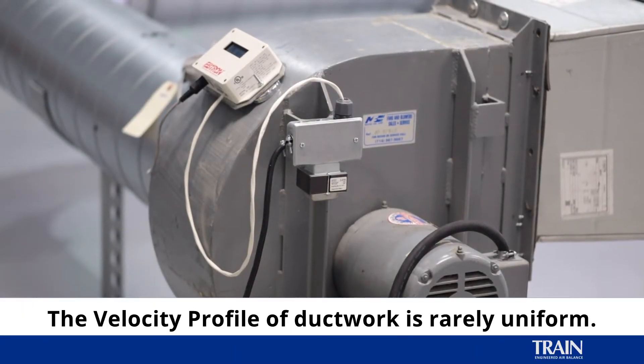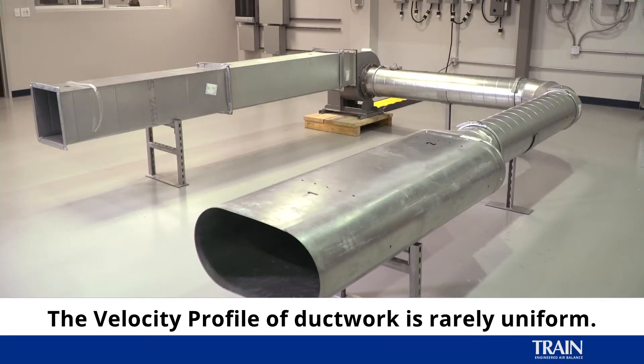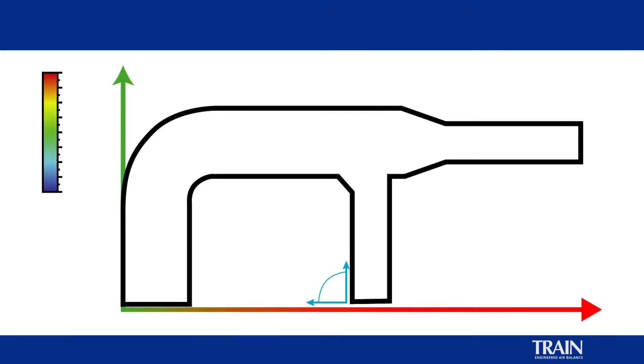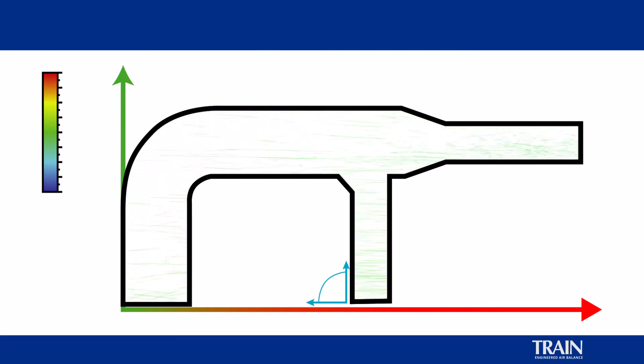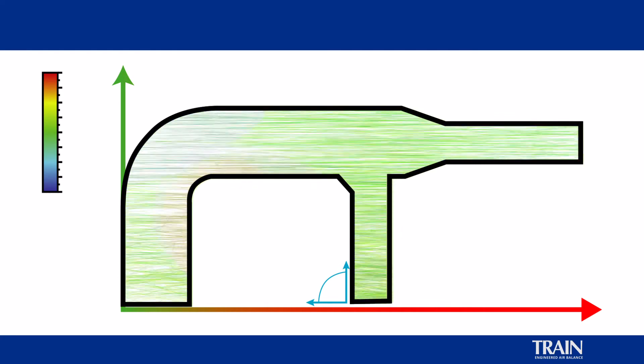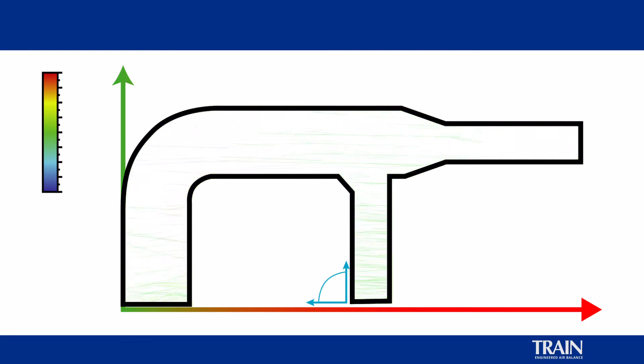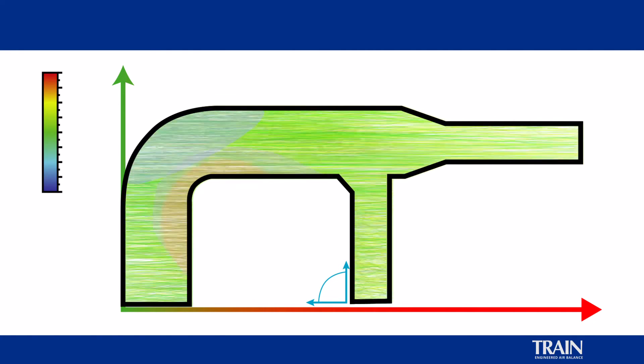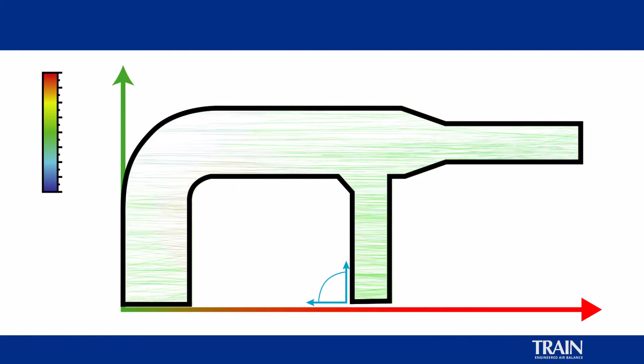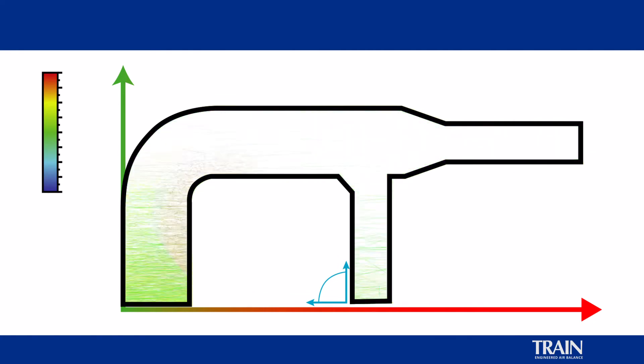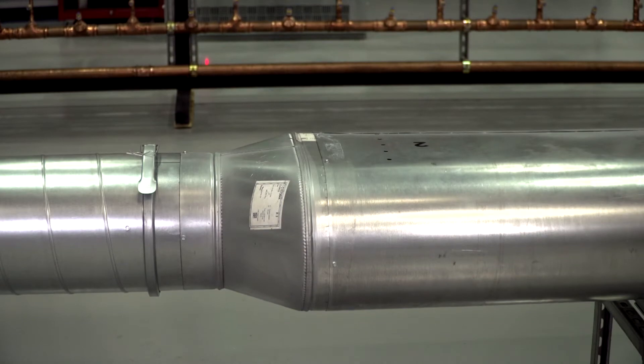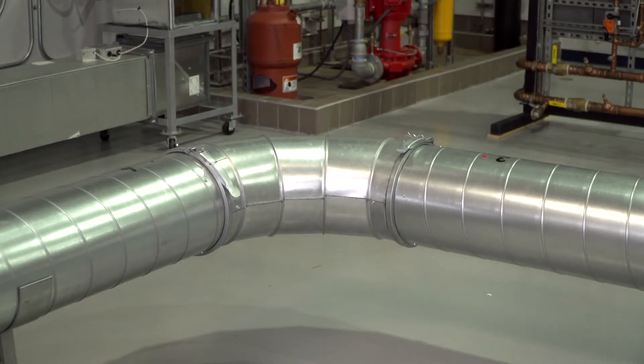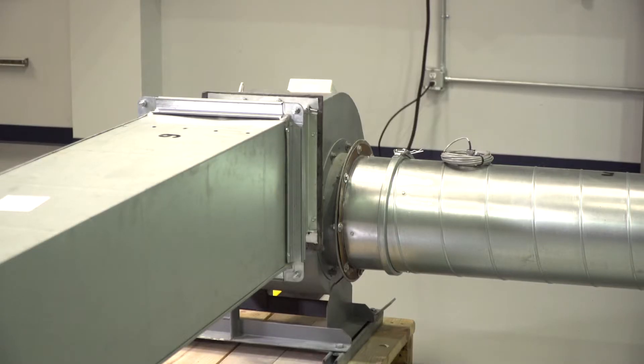Let's talk about velocity profiles in ductwork. Rarely is a velocity profile uniform in the ductwork. Typically, as the air flow flows through the ductwork, it has higher velocity in the center and lower velocity at the edges due to friction. There are quite a few things that can change the characteristics of the velocity profile, including duct transitions, elbows, and proximity to fan inlets and discharge effects.